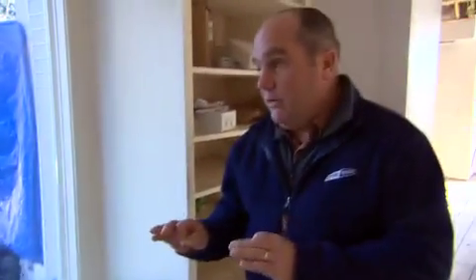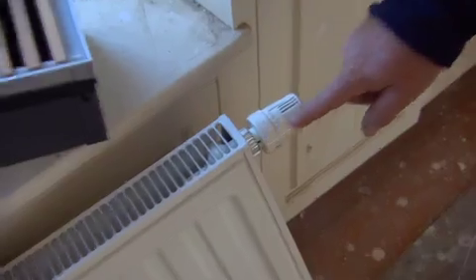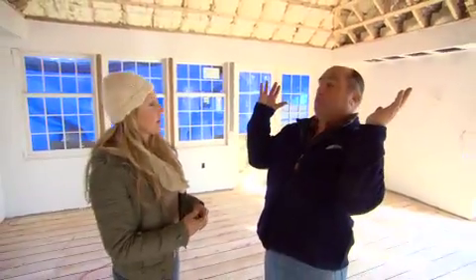Zoned every single radiator, every single room. The entire system has a central brain that puts just the right water temperature into the building proportional to the temperature outside. Most heating systems in America are actually controlled by having a gas pedal at full blast and then a brake — the thermostat comes on, heats up the whole house, overheats it, and shuts off. We just want to keep up with the heat loss as it happens, so as you walk into a room, it's always just the right temperature.